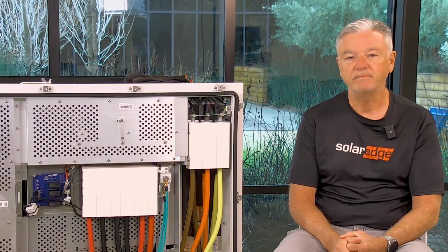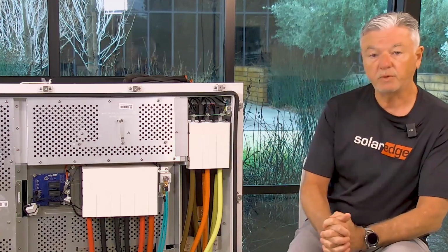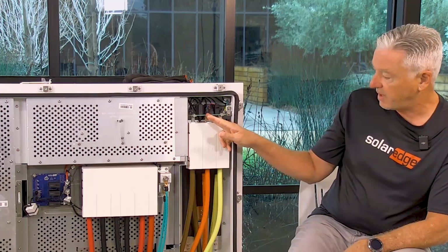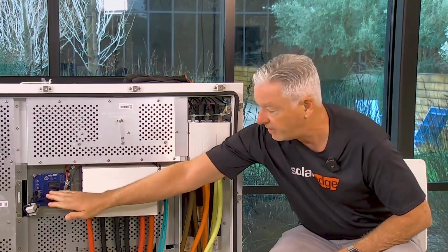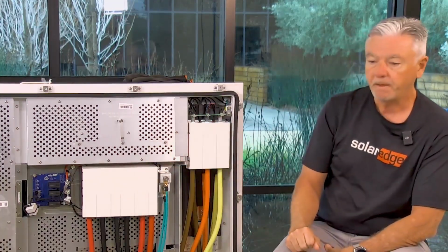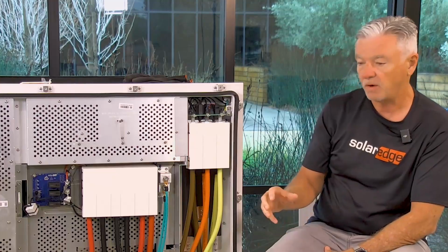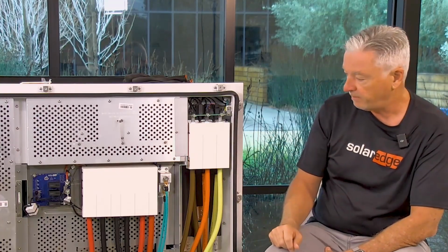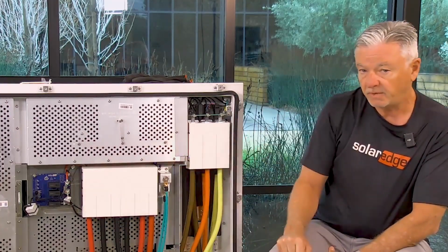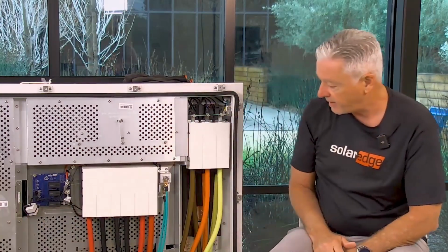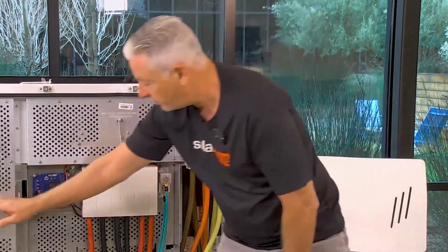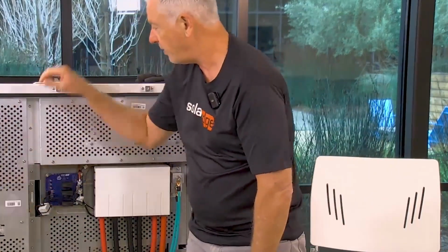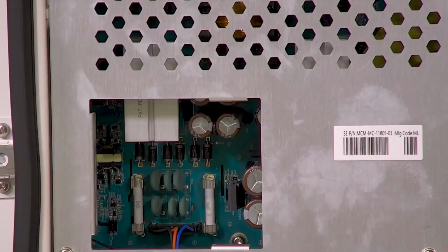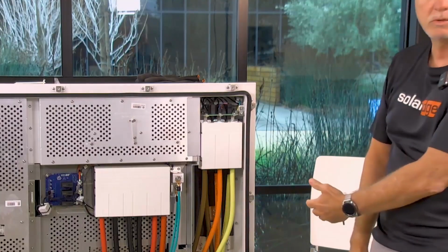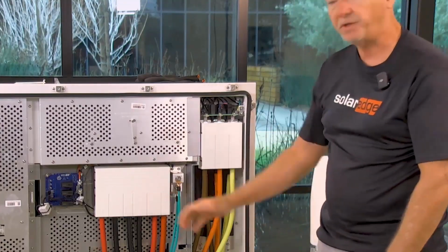What parts of the inverter are field replaceable? So there are a few parts that are field replaceable, yes. You see these surge protection devices here on the AC side and the surge protection device here on the DC side. These are field replaceable. They're a one-time use, a sacrificial device. So when there is a surge, then they need to be replaced. There are 2 fans internal to the inverter, and one is located here and the other is located there. And also behind this little door right here, there's typically a panel. There are some fuses for the auxiliary board that is behind this little panel right here. So those are all field replaceable. On the bottom there are some external cooling fans, 6 of them actually. Those are field replaceable.